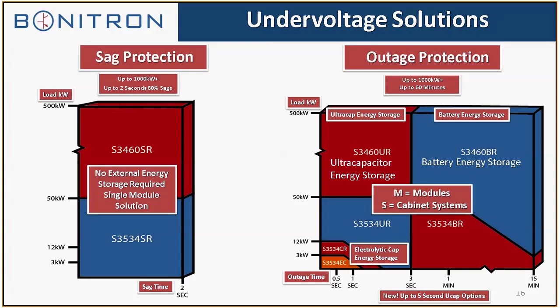This is how we specify the ride-through: kilowatts to time. It's that simple. What's the amount of kilowatts for the motor? Ride-through can be sized to the motor, even more so than a braking solution or overvoltage solution, because all we're doing is holding up the motor during a utility power event. So you don't have to put in that 150% that you do with a braking solution sometimes, depending on the peak braking power. All we're doing is sizing it to what the motor requires to run the process. It has nothing to do with regenerative energy. We're just keeping the bus at a stable level.